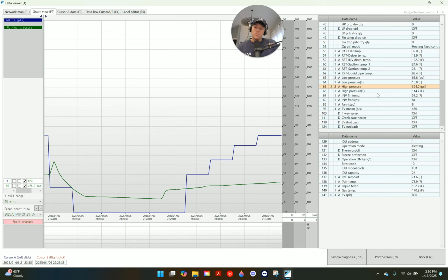Now, it's a one-to-one application with a slim ducted unit. There is no air restrictions. The filtration is good. Static pressure is a little bit high, but the unit is operating fairly well, actually. And again, he has no heating issues until the random error codes that he's gotten. It's gotten a lot worse than it was last year. And this year, it's actually pretty bad to the point where he's having to reset it almost every week.